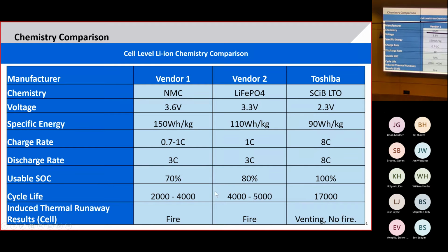Cycle life: 4,000, 5,000, 17,000. And then with UL 9540A testing, it was proven again that there is no fire, no smoke. There is obviously venting, because you have volume, it's enclosed, you put pressure on it, you put temperature on it, something's gonna give, so it vents.